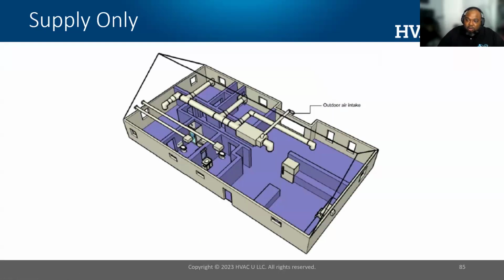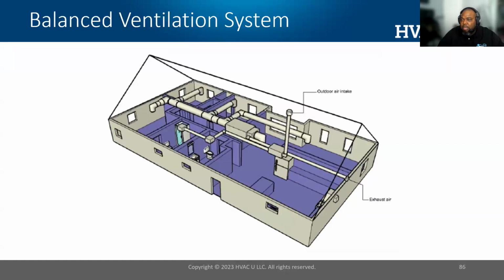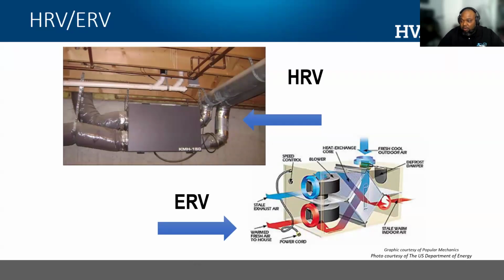Right? Supply air only. I'm bringing in air from outside. I'm bringing it in and I'm going to supply it to my different areas. Supply air only. Again, I'm going to bring in air from outside. 1 CFM in, I push the conditioned air out. When I push the conditioned air out, I've got to pay to recondition it. And this is a form of balance where I have supply, exhaust, and air coming in from outside. Balance, but my favorite is the HRV and ERV.